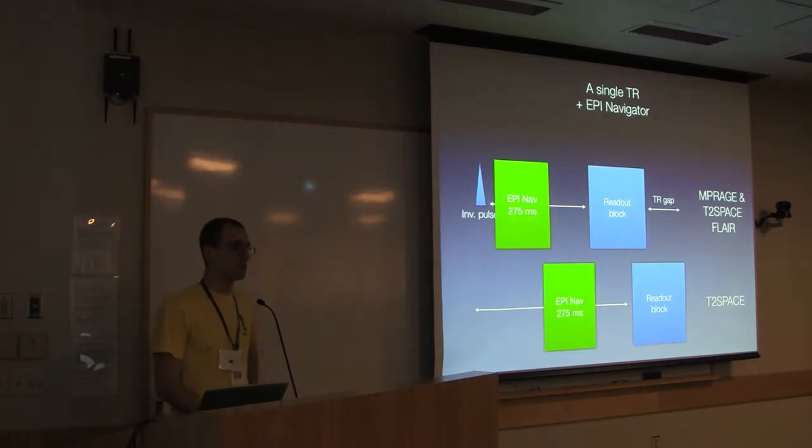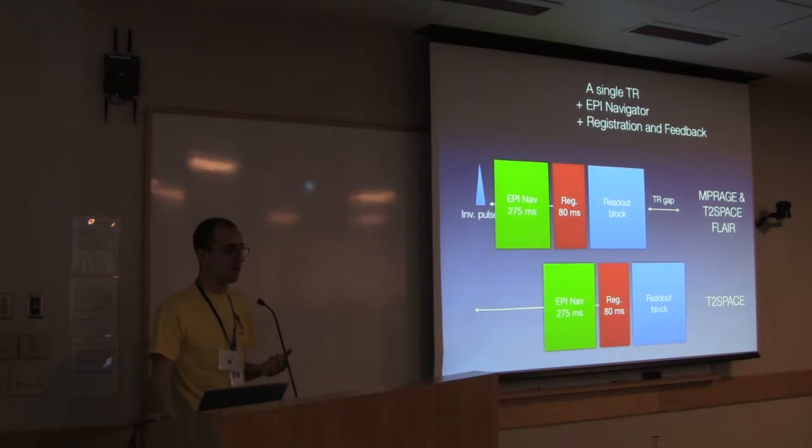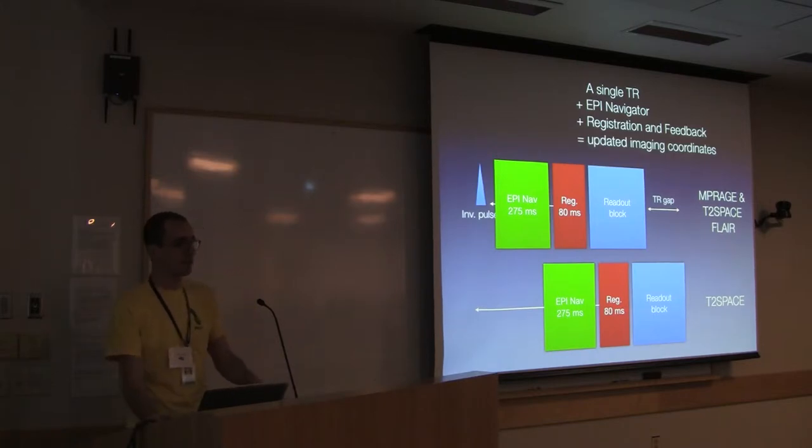What we do is in all that dead time, we stick in an EPI-based navigator. We can get a whole head volume in about 275 milliseconds. Then we do, on the scanner, we do image registration and feedback our estimate of where the person's head has moved. That takes us about another 80 milliseconds to do the registration and feedback. The combination of doing this every TR gives us updated imaging coordinates. We get a new image that tells us where the person is, we register, we feed it back. We change the imaging coordinates so that now our MP-RAGE is actually imaging in head coordinates wherever the person moves their head, instead of stuck in standard coordinates or wherever you put them when you hit go.